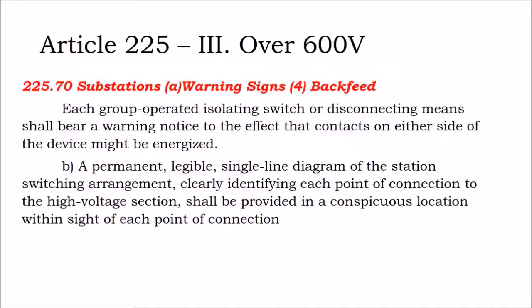And when you get into, say, commercial design, and you might think, well, what are all the signage requirements that I'm going to have to get into? Here you see a call out that says, well, for substations, which are higher voltage systems, I need to have a plaque with a single line diagram identifying the points of interconnection. And it's not uncommon on commercial inverters that are going from the 600 volts of the array into the 480 voltage of the utility primary to put a single line diagram around the inverters as well.